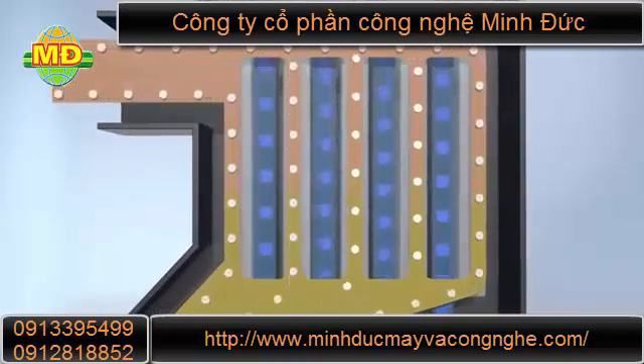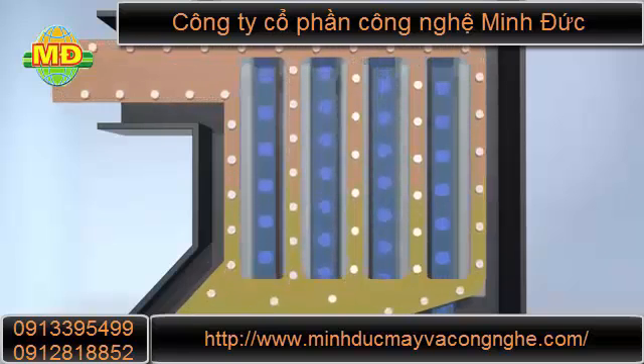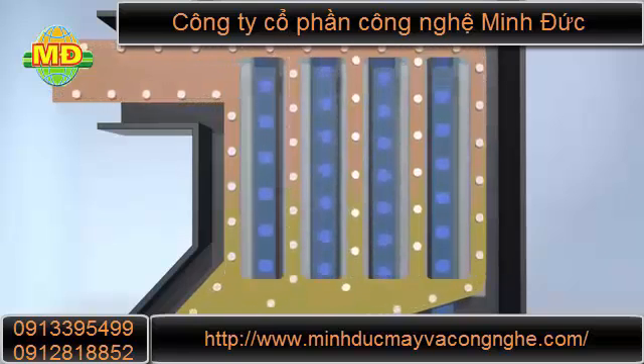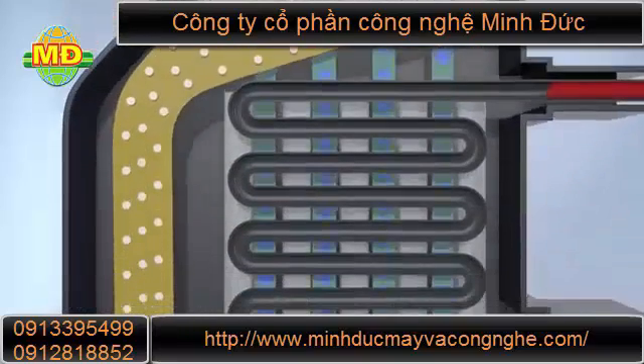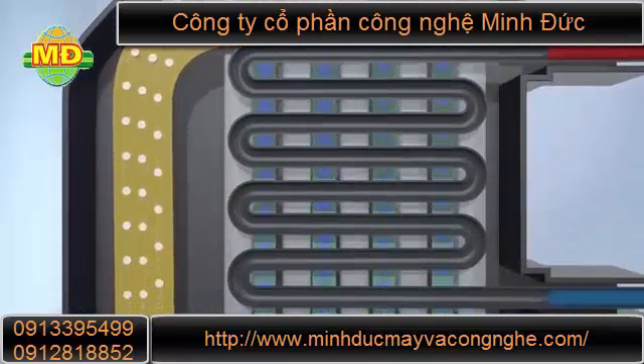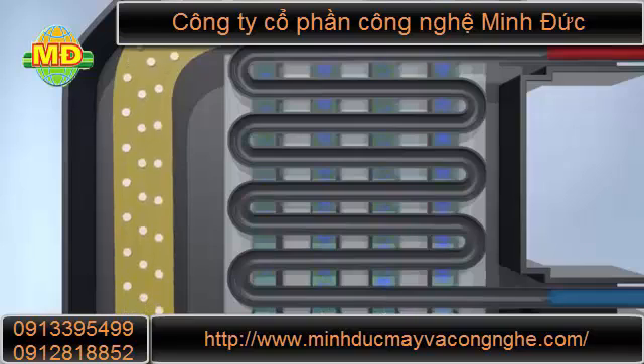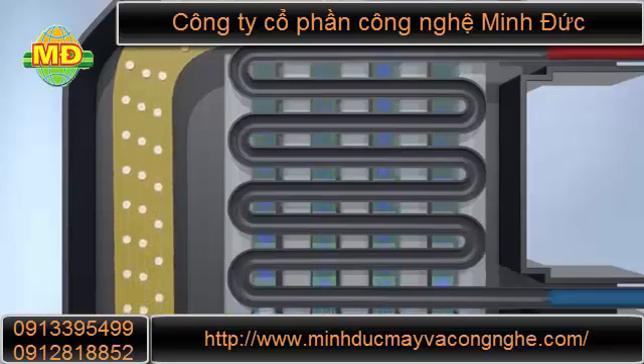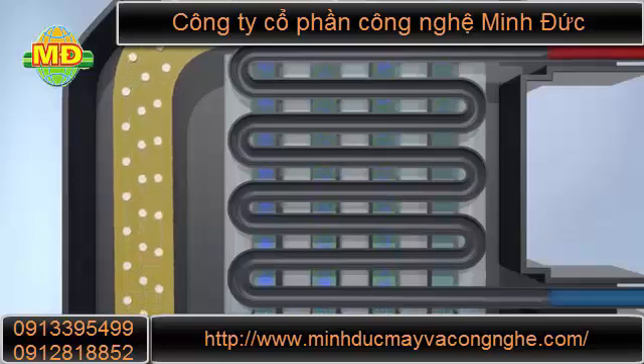There, it is pre-cooled in a countercurrent process by already dry and cooler air. It then flows through the actual cooler, in which it is continuously cooled down to approximately 3 degrees Celsius. The cold temperature reduces the compressed air's ability to absorb water.